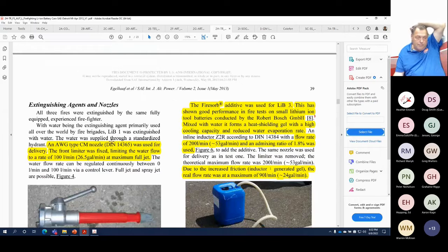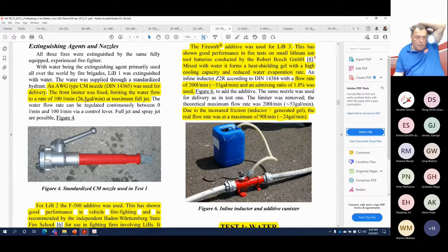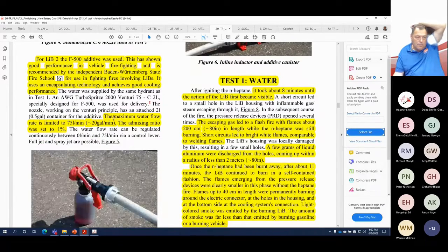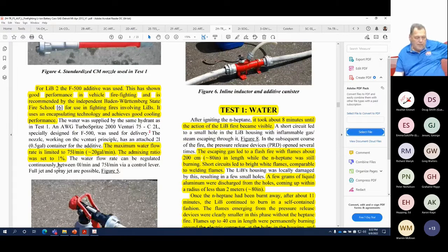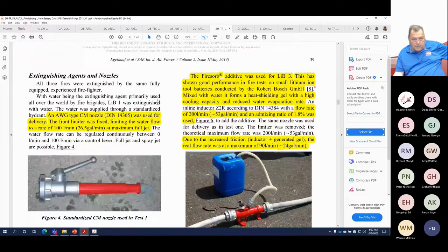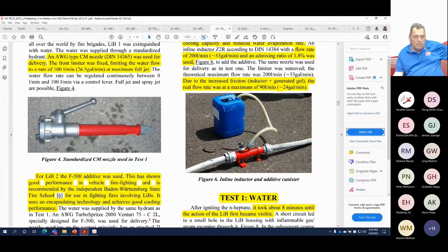It talks here about the different nozzle types that were used. This was a 100 liter per minute nozzle. Here we used the 75 liter per minute, with a ratio of 1%. In Europe, they've been doing testing at 1 and 2%. Here in the US, we recommend 3% because our listing for Class B is 3%, and our encapsulation ratio is 2.5%, which I can address in a minute. So here they talk about FireSorb having good fire performance on the small lithium-ion batteries, conducted by Robert Bosch. Mixed with water, it forms a heat shield gel with a high cooling capacity to reduce the water evaporation rate. So this is the FireSorb product.